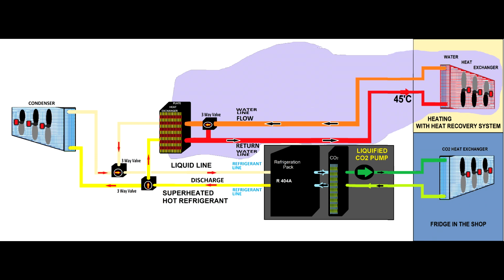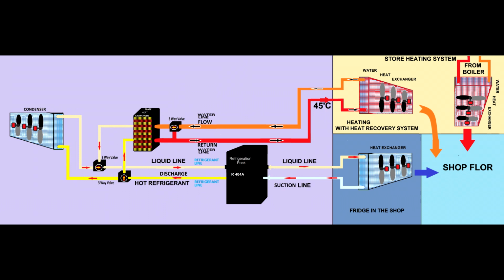I came across Marks and Spencer stores which have only a heat recovery system fitted, and they would expect in the middle of the winter to have a warm store, and that concept ended up in a disaster. Like I said, if you choose not to have a boiler in line with a plate heat exchanger that recovers the energy from refrigerant, you have to have a separate source of heat, either from the boilers or a heat pump, whatever, but you have to have a source of heat, because the refrigeration equipment will absorb a lot of energy, leaving a very cold shop.